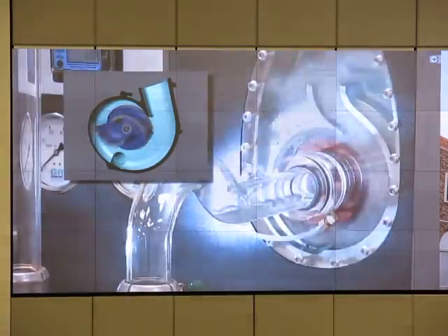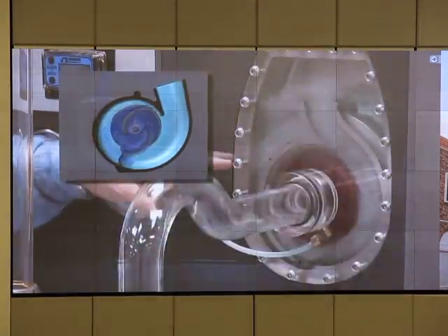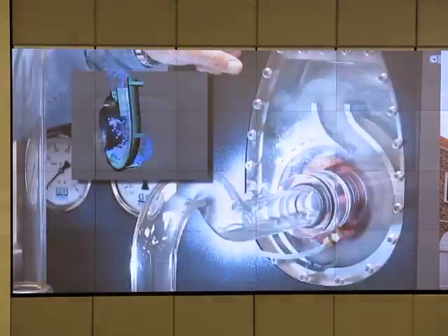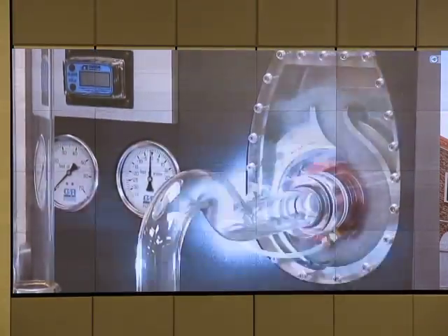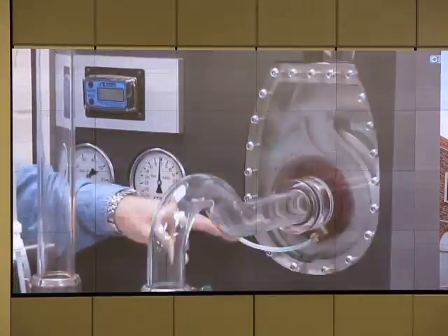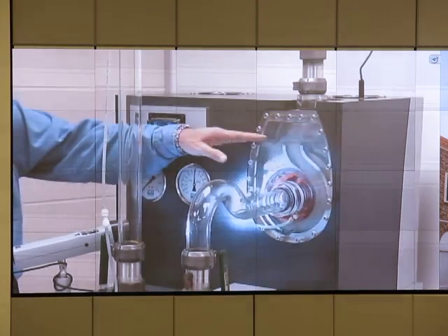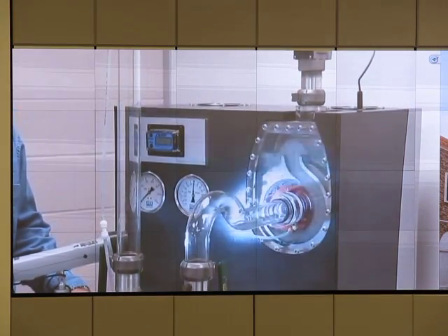Inside this discharge chamber, the air and water separate. The heavy water falls back down through a recirculation port, and the air then is evacuated through an open-ended line or through an air release device. All the while that we recirculate the water inside the casing and remove the air from the top, we create a low pressure at the eye of this impeller.